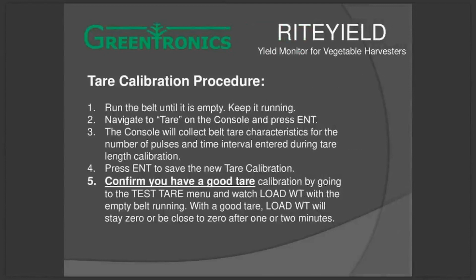The next step is really important: you have to confirm that it actually knows where zero is. Go into the test tare menu and look at your load weight while the conveyor is running. It should stay around zero, though it might fluctuate a bit since the belt's weight isn't perfectly consistent along its length. You'll see some positive numbers, then some negative numbers, but after a few minutes it should still average around zero.